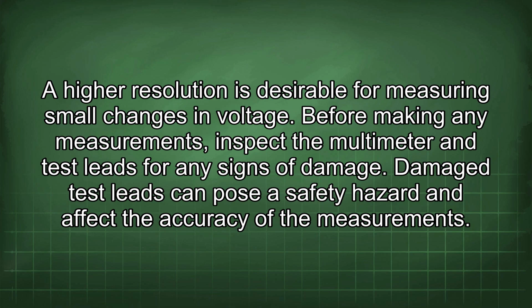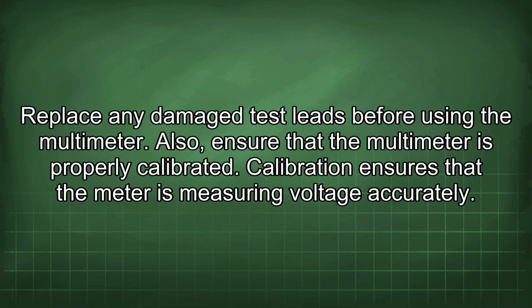Before making any measurements, inspect the multimeter and test leads for any signs of damage. Damaged test leads can pose a safety hazard and affect the accuracy of the measurements. Replace any damaged test leads before using the multimeter. Also, ensure that the multimeter is properly calibrated. Calibration ensures that the meter is measuring voltage accurately.